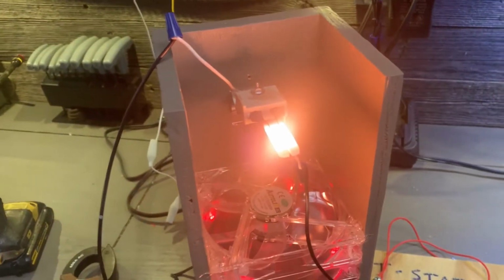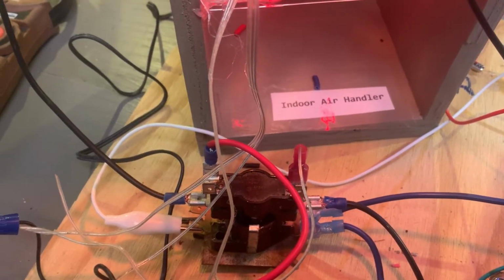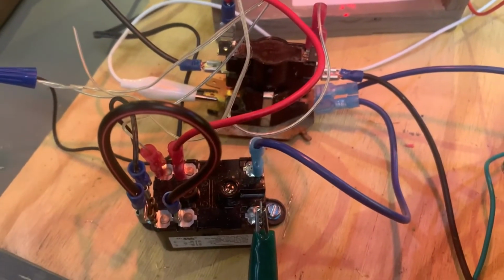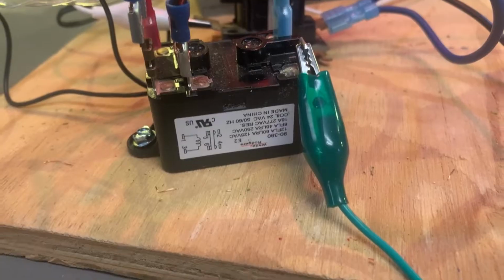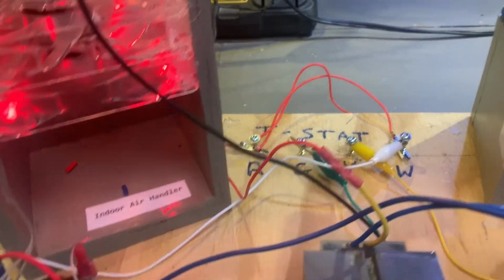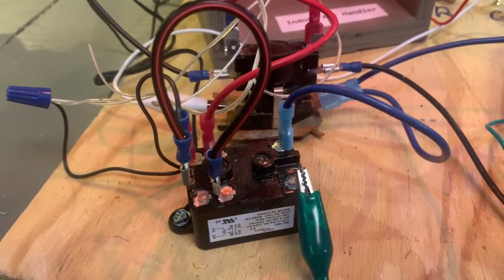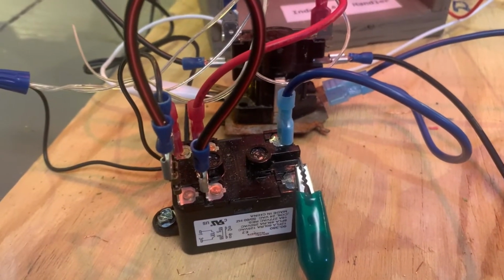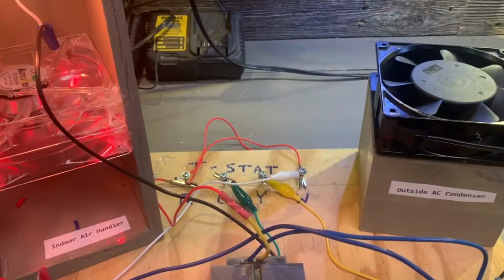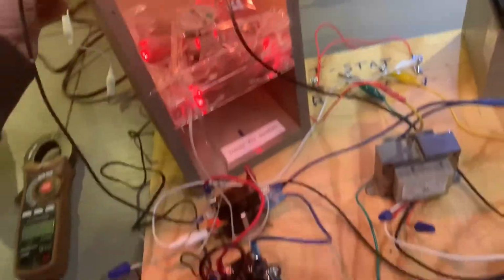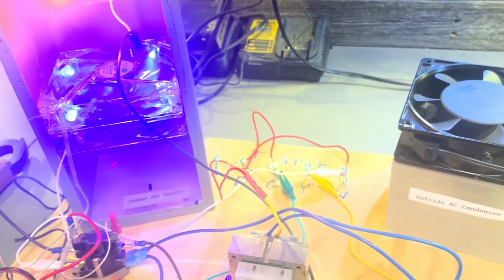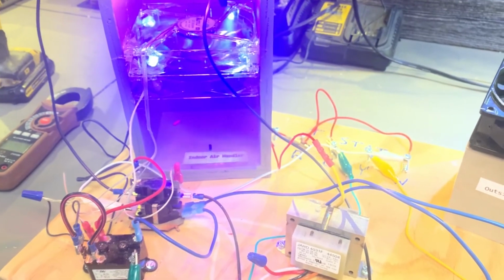Okay, so there's our heating fan for the red, and then our hot surface igniter, which also goes through the sequencer. One of the things that's going on with the red fan for heat is that the sequencer activates it, but power for that fan is also looped through the normally closed contacts of the fan relay. So what happens is, if green fan is called for, it disconnects power to the red fan and shifts it over to the cooling fan. And we can go over here to the thermostat and show you exactly what that looks like. So we're still running in heat, but we've activated the fan relay at the thermostat. So that disconnected the power going to the heating fan.